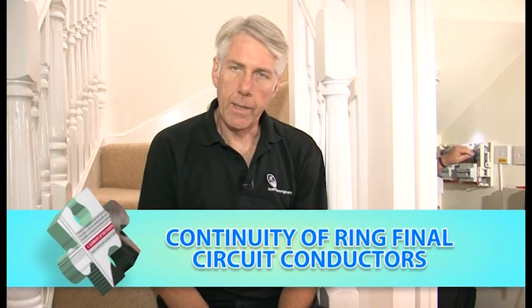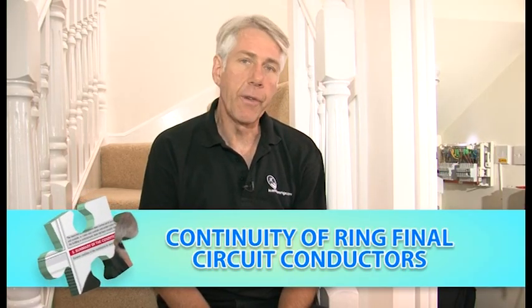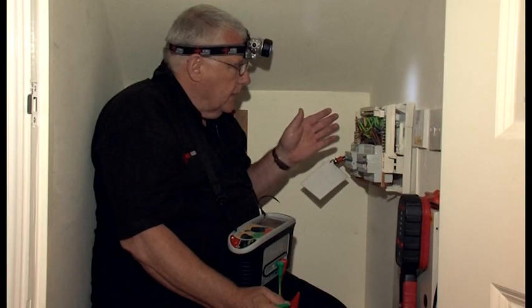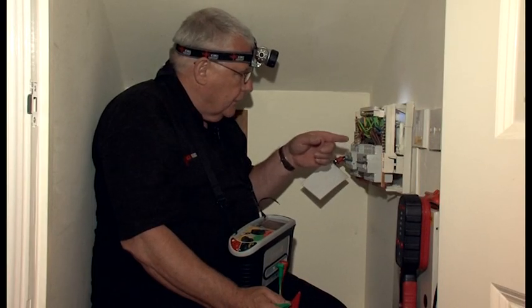Our next dead test is to verify the continuity of ring final circuit conductors. Although we verified that the CPCs are present as part of the R2 tests and visual inspection, it's vital with ring circuits to make sure that the CPCs, lines and neutrals are actually connected into a ring. If not, this circuit will not be able to carry the full load expected of a ring circuit. Tony has also left the main protective bonding conductors disconnected to help eliminate any parallel earth paths through metallic pipework and the like. Now I've disconnected both legs of the ring, as you can see.